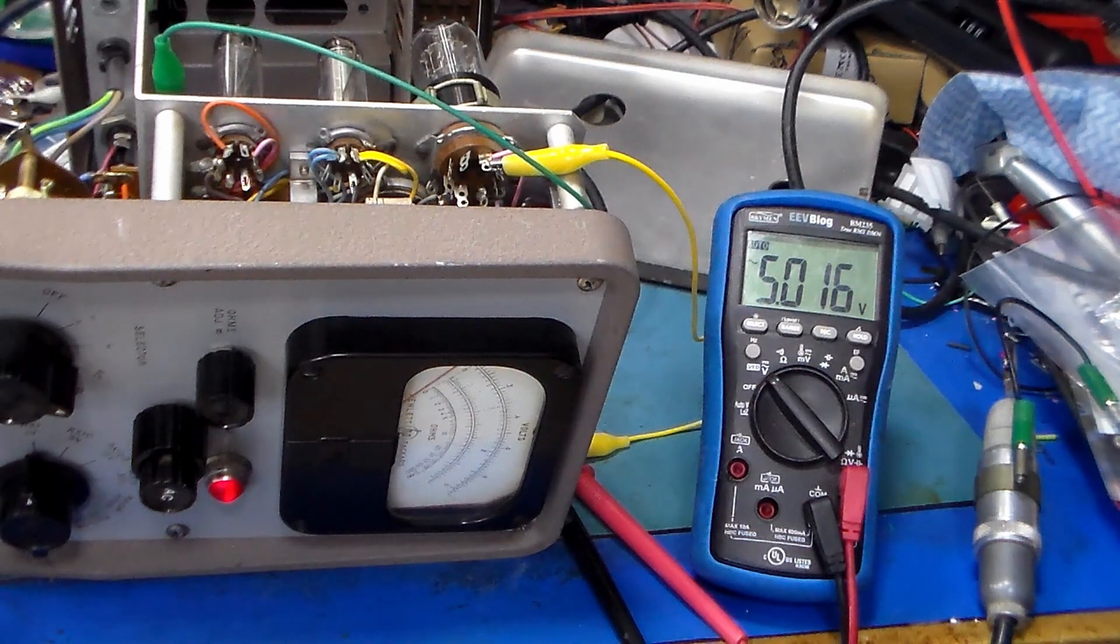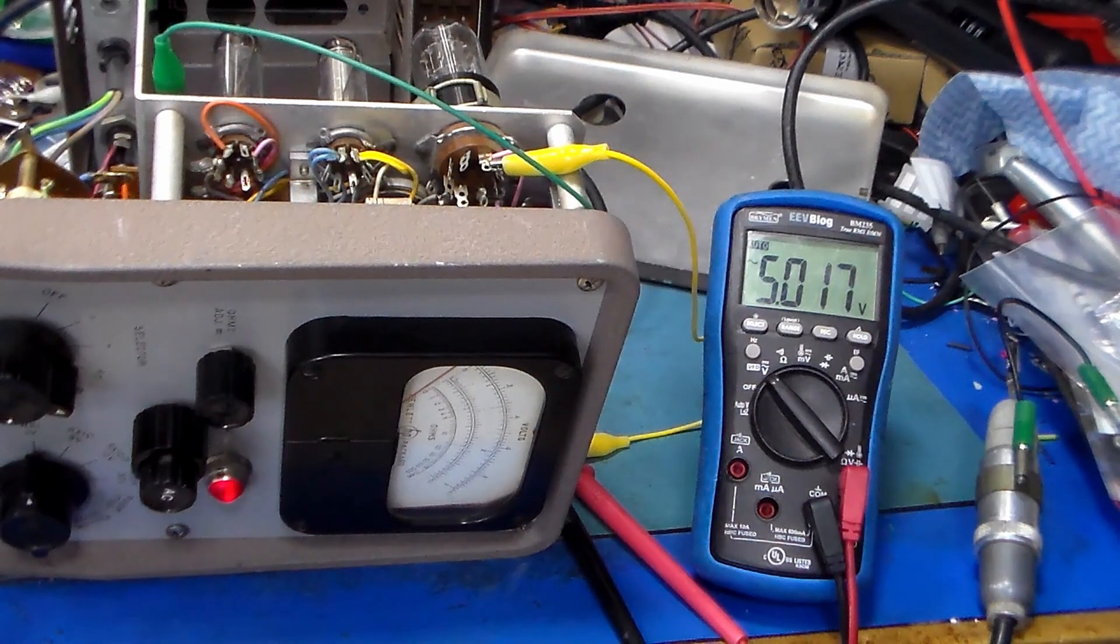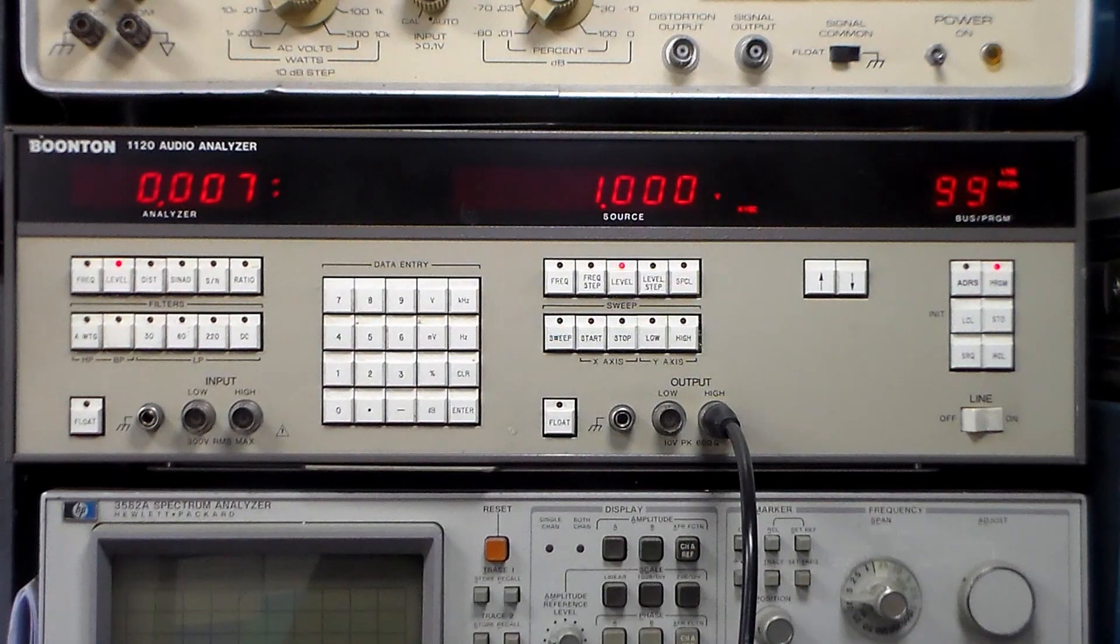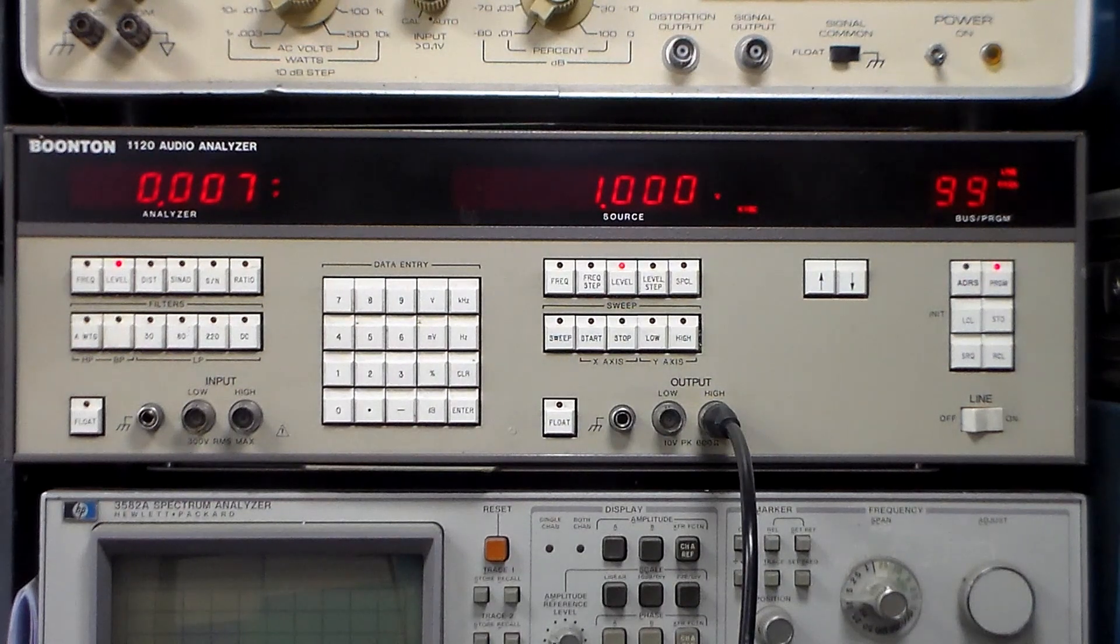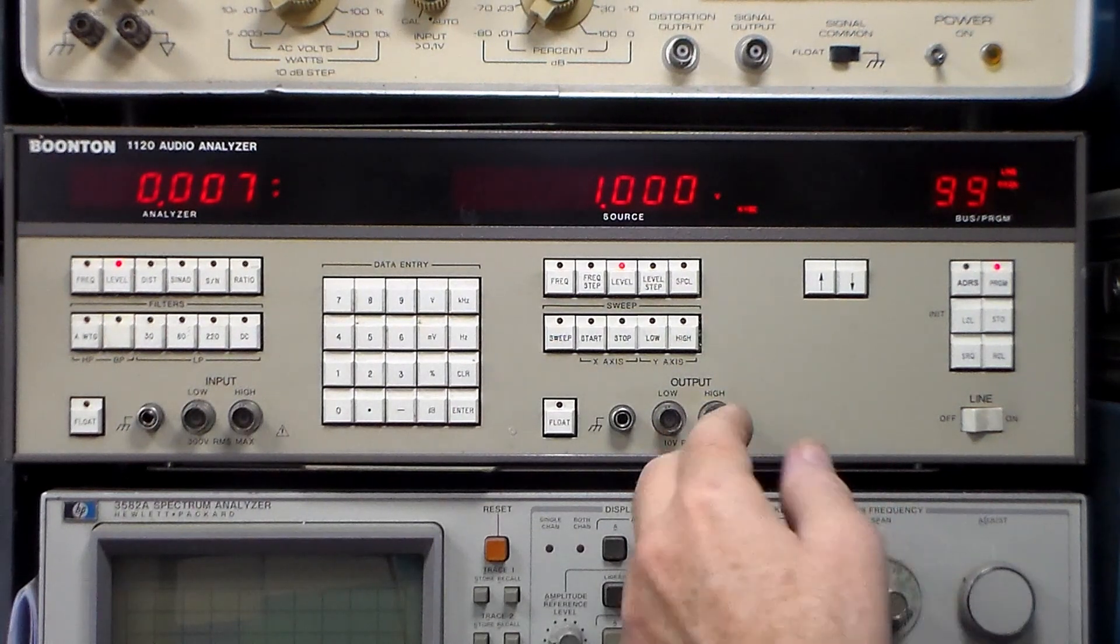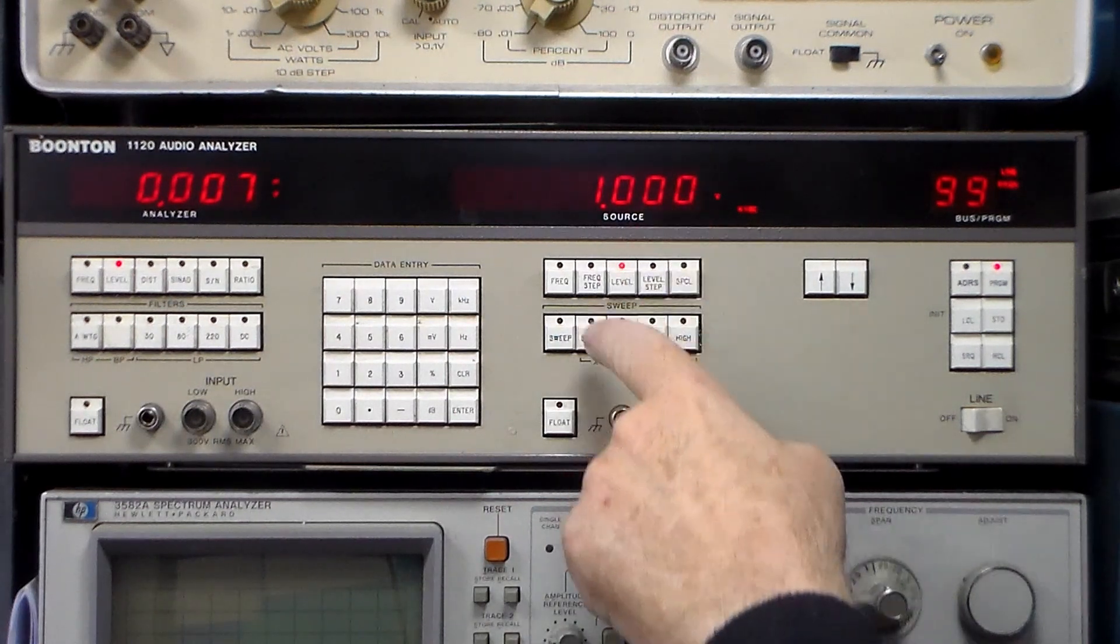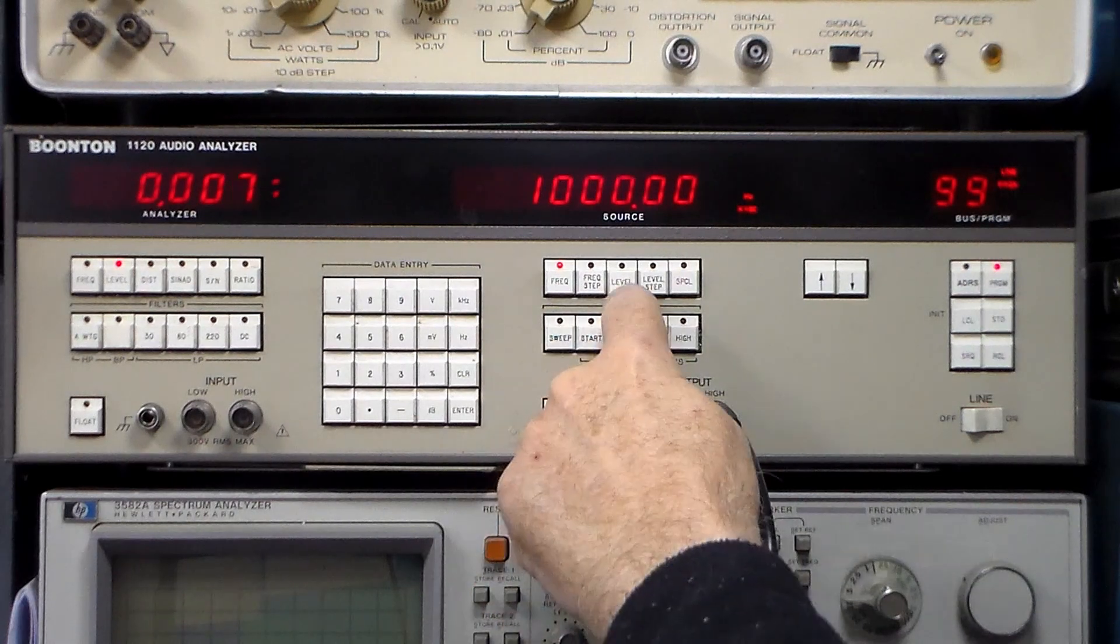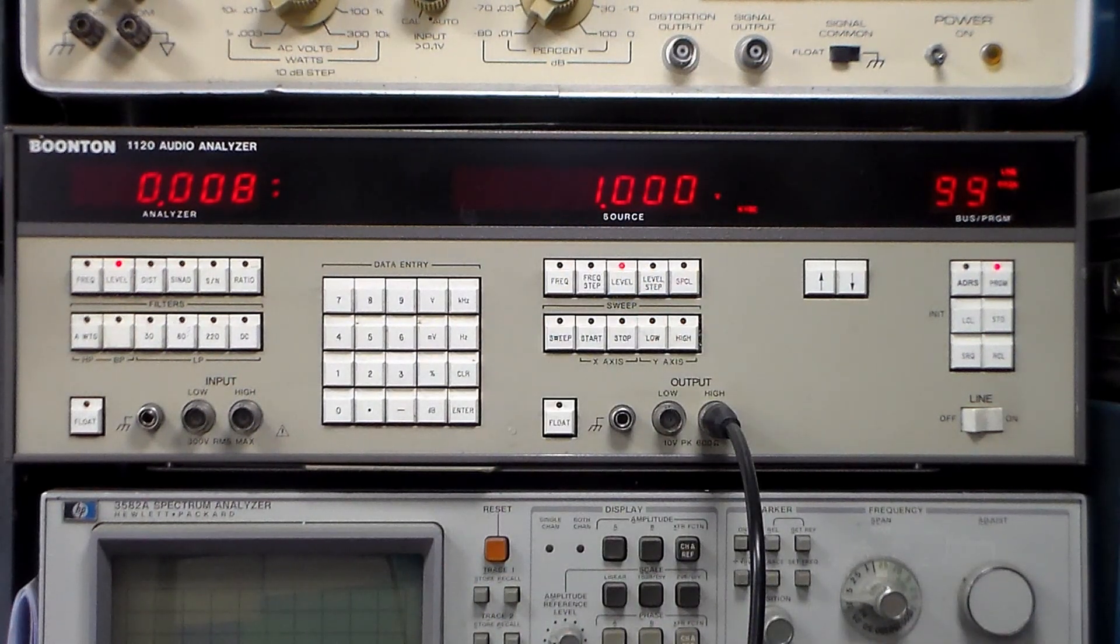Now we're ready to actually start checking calibration of the AC section. To check the AC inputs, I'm only going to check low voltages and a relatively low frequency. We're using a Boonton 1120 audio analyzer, just the generator section. It's displaying level at 1 volt RMS and it's set up for a frequency of 1000 Hz. We'll use this to go up to about 6 volts on the low ranges of the HP 410B.